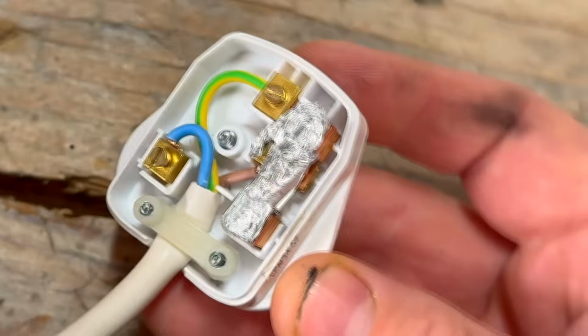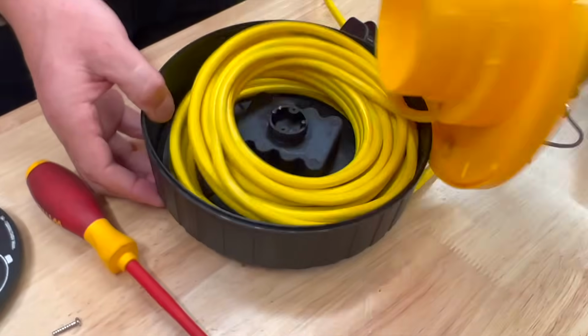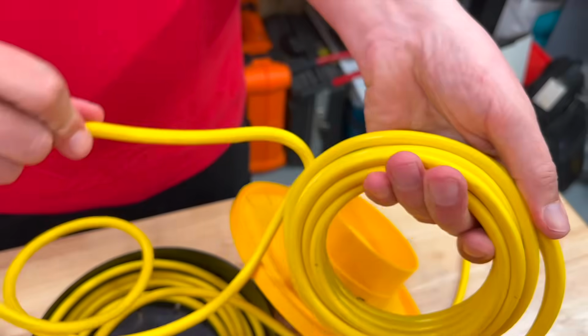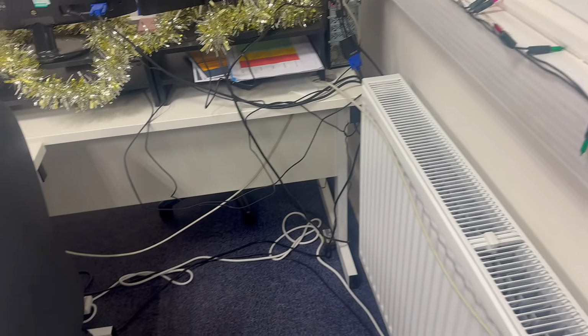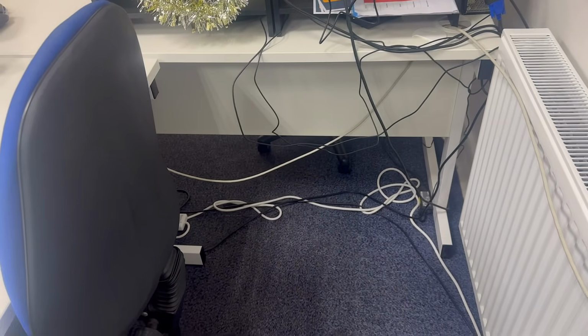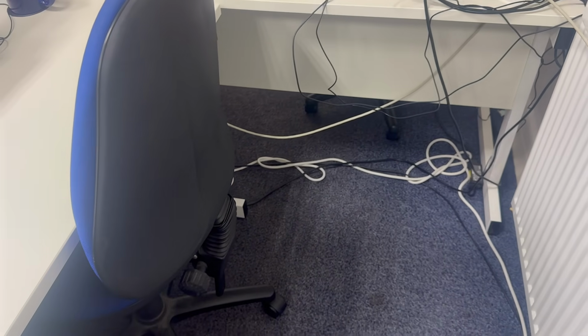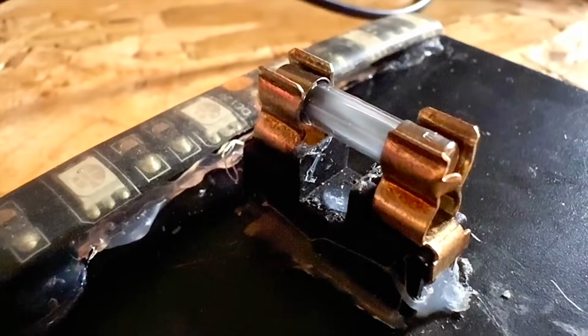So back to the fuse. Is it there to protect the appliance? Well, and this may come as a surprise, no. The fuse protects the cable feeding the appliance, not the appliance itself. Think of it like this: if you have a cable coiled up behind a desk that you can't see and it begins to deteriorate and potentially catch fire, then we want the protective device to operate in that circumstance.